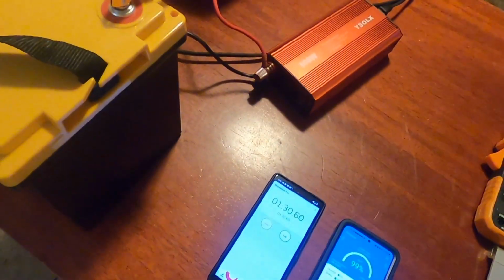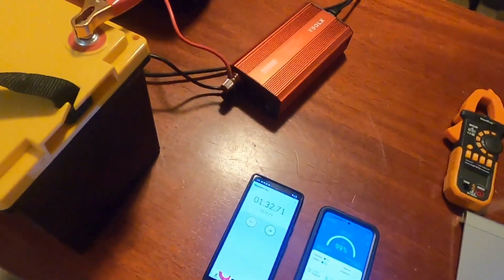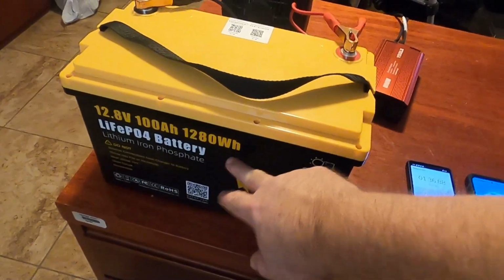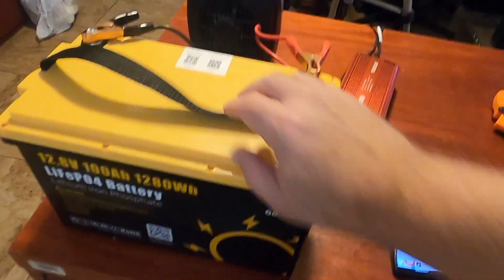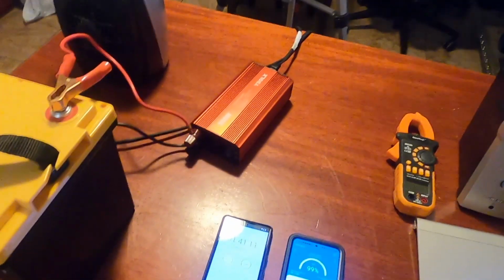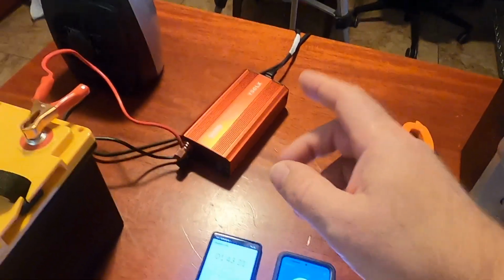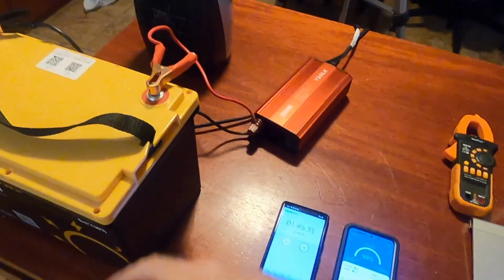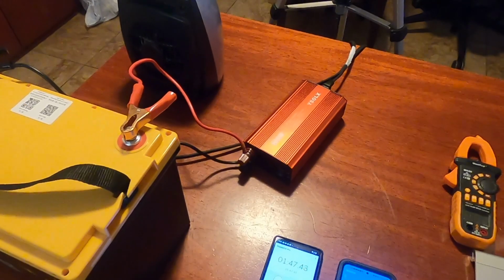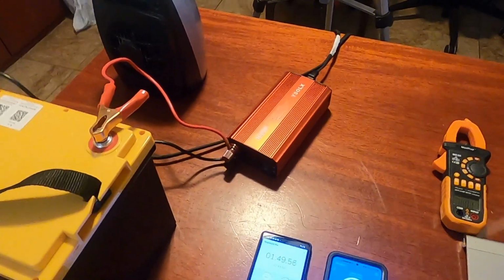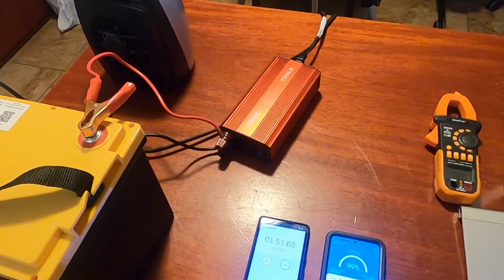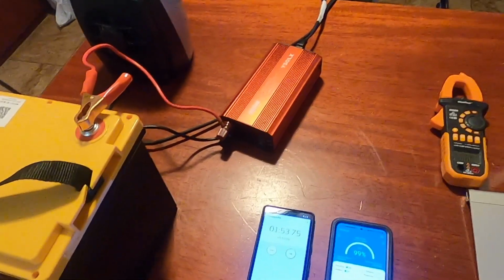Okay, so from that I know my amps, I know what my nominal voltage is, and I know I've got 1280 watt hours worth of capacity. So from all of that I can figure out what the load is, and I can divide that load into the watt hours of the battery, and figure out how long this should run. Let me make a few calculations and we'll get back.